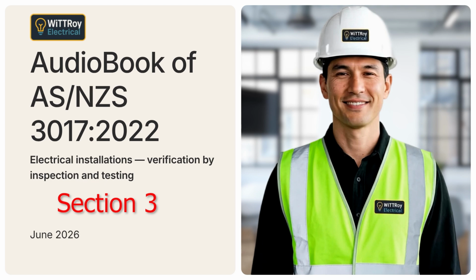The inspection must also consider whether an earthed situation has been created that may require additional electrical equipment to be earthed. In simple terms, earthing inspection is not only checking for a green and yellow conductor, it is checking that the whole earthing and bonding arrangement is correct, continuous, identified, connected, and suitable for the installation.